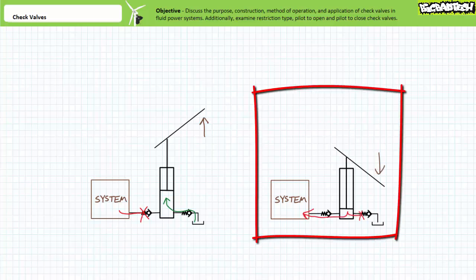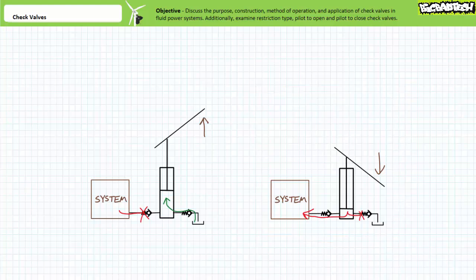In contrast, when an operator pushes the manual pump handle downwards, the contracting cylindrical volume created by the barrel and moving piston creates a region of higher pressure and pushes fluid out of the cylinder and into the system via the outlet check valve permitting free flow.